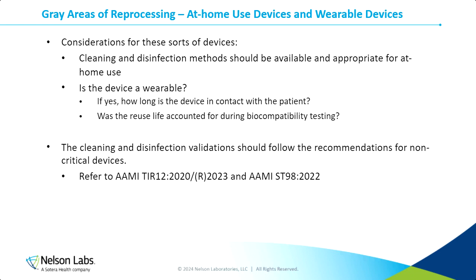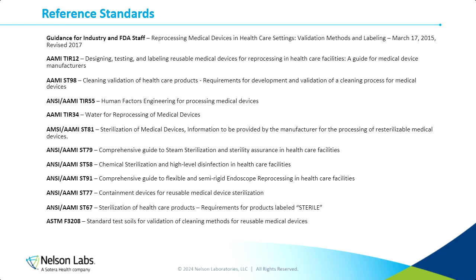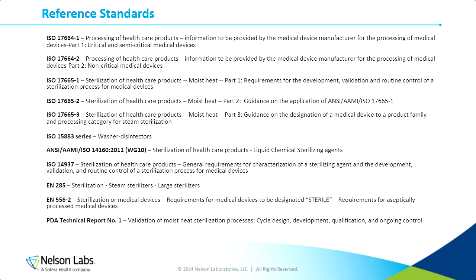When it comes to the cleaning and disinfection validations of these devices, I would refer to AAMI TIR12 and AAMI ST98 for just the current guidance and that FDA guidance document from 2015. Now, if you have a reusable medical device that you're developing, I would definitely recommend that you refer to the standards here. There are a lot of standards out there concerning cleaning, disinfection, and sterilization of reusable medical devices. But definitely be aware of them and familiar with them as you're developing your reusable medical device.